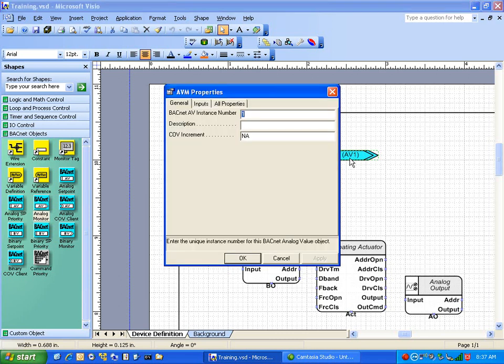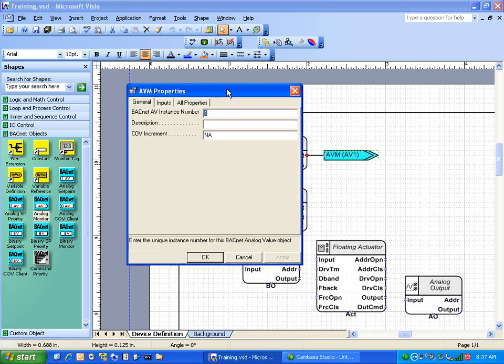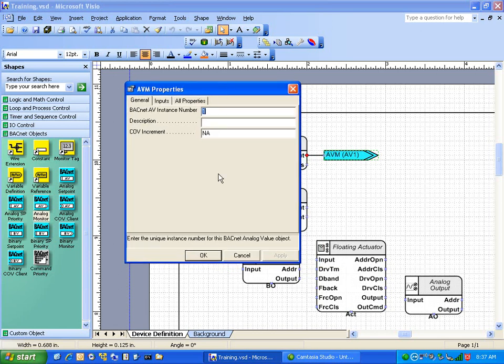Similar to the inputs, if you just double click and go into its properties, again, it's another value. It's going to be another COV increment. So what you're going to find is the setup in Workplace Tech is going to be more of a precision type setup as you're doing your Workplace Tech programming. But again, like I said, you're saving a lot of time up in the graphics level, especially when you're in the projects department, and you're just pumping out 80 gazillion graphic screens every other week.